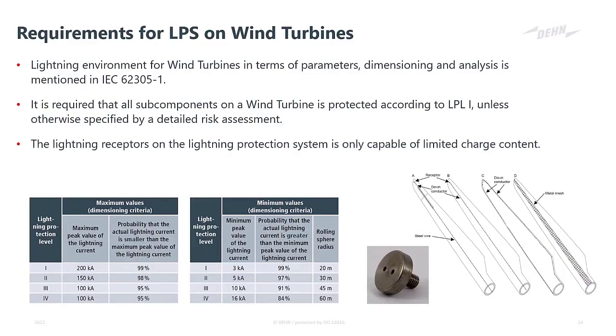Now, to mitigate the risk, we first again have to fall a little bit back on the standards to understand some of the terminology. The lightning environment for wind turbines and the parameters associated with lightning current within wind turbines and dimensioning and analysis of the lightning protection system is mentioned in the IEC 62305 standard in part 1, and this is shown here, where lightning protection is made up of 4 levels. We have level 4 being the least amount of protection, and level 1 being the most amount of protection, or the best and highest level of protection.